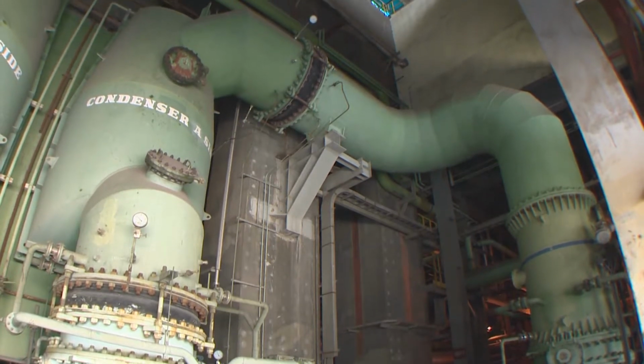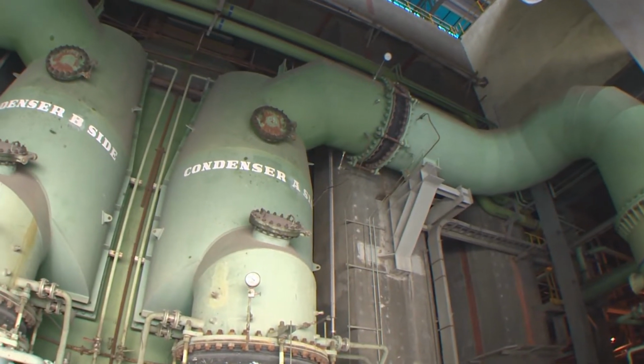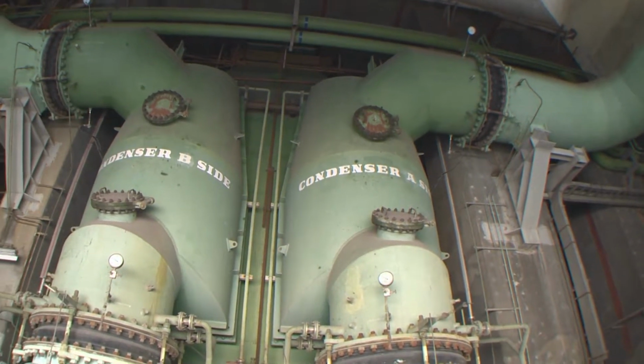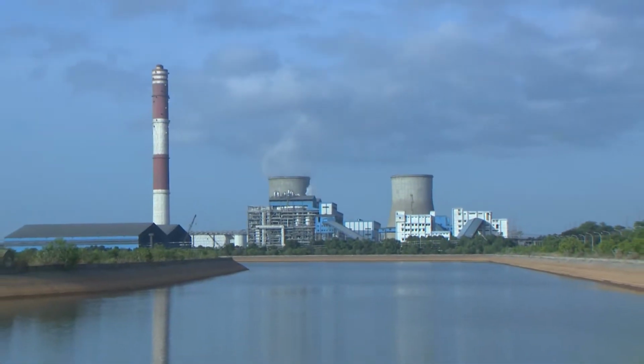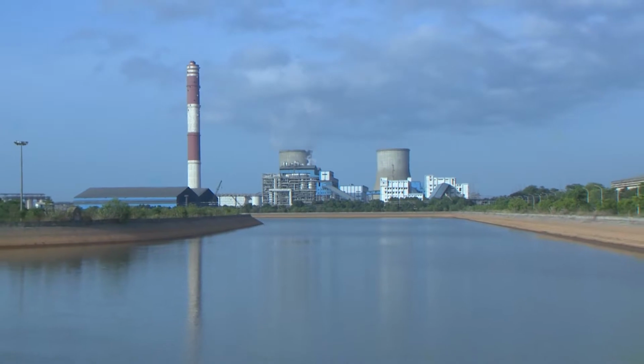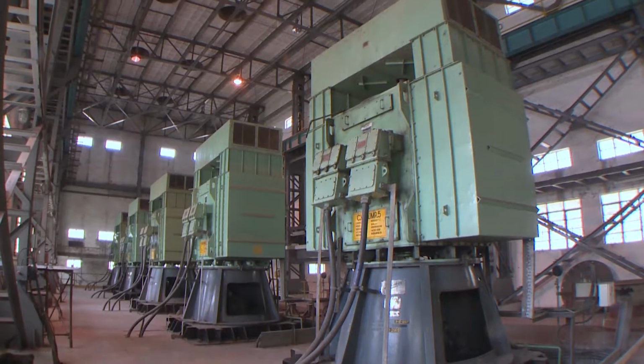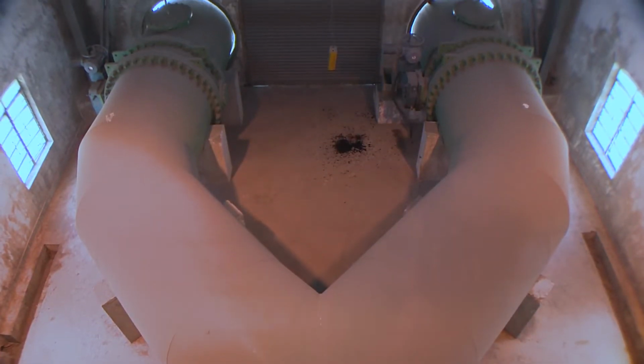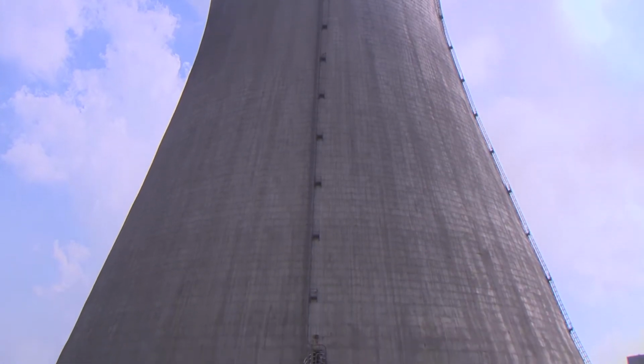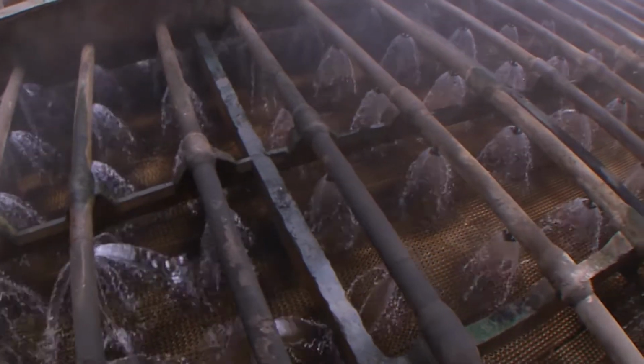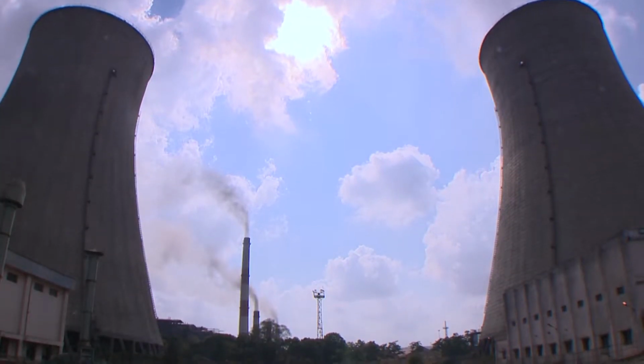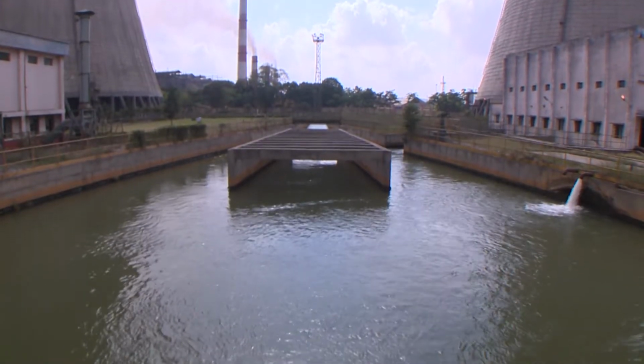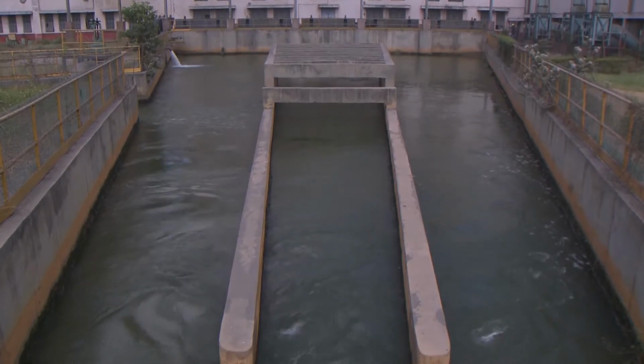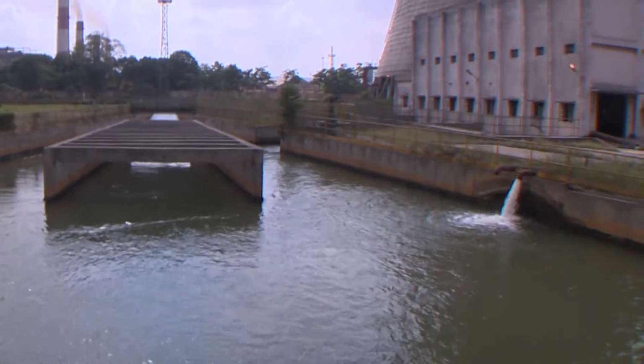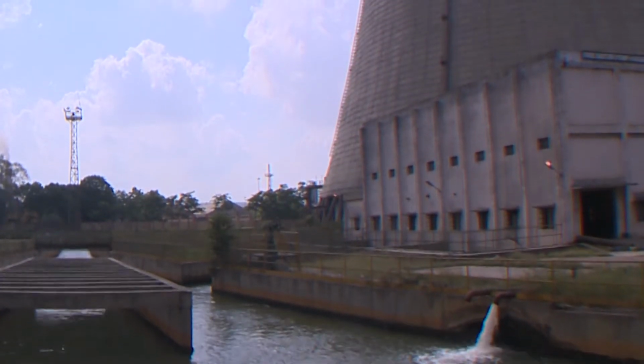Circulating water system. The circulating water flows through the condenser tubes and takes away the heat from the exhaust steam of the LP turbine, thereby condensing it. The water pumped from mines and stored in the circulating water lake is used as cooling medium. The circulating water pump will pump the water to the condenser through large size pipelines. This water removes heat from the condenser and becomes hot and then goes to the natural draft cooling tower for cooling. The cooled water from the cooling tower basin will flow back to the circulating water pump house by gravity through an open channel. Then it will be pumped again to the condenser. The losses in the circulating water are made up directly from the circulating water lake.